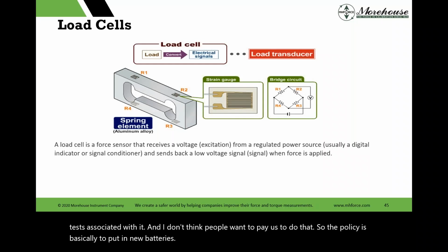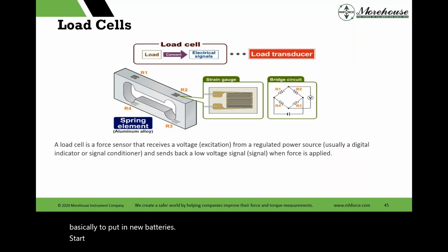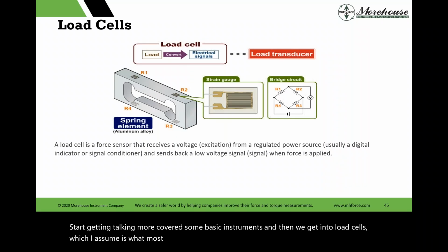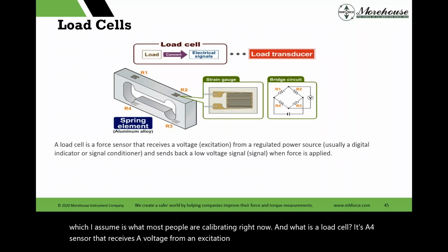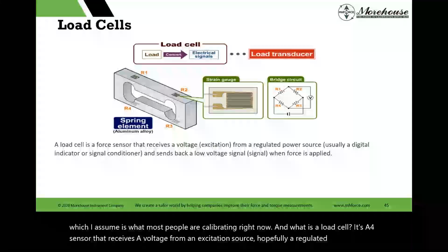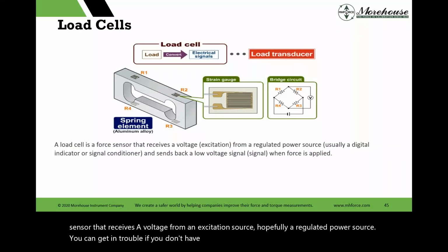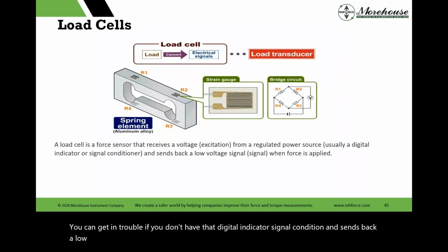We start talking more, covered some basic instruments, and then we get into load cells, which I assume is what most people are calibrating right now. And what is a load cell? It's a force sensor that receives a voltage from an excitation source, hopefully a regulated power source. You can get in trouble if you don't have that. Digital indicator signal conditioner, and sends back a low voltage signal when force is applied. It's basically a transducer, converts one type of energy into another.